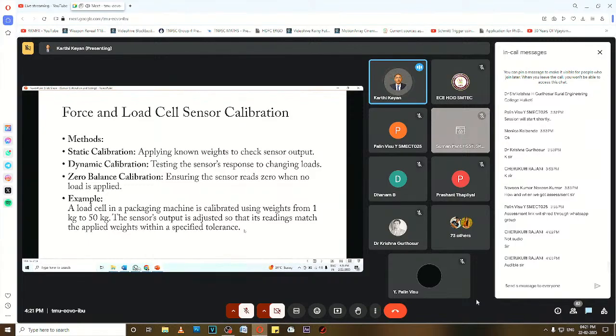For example, a load cell in a packaging machine is calibrated using weights from 1 kg to 50 kg. The sensor's output is adjusted so that its readings match the applied weights within the specified tolerance. Here I have marked the tolerance for the readings. If it is 1 kg, then 999 grams doesn't matter, or 1001 grams would be an acceptable range. If it goes beyond that, like 1010 grams, or below, like 980 grams, it wouldn't be acceptable. So the specified tolerance also has to be checked before these readings happen.